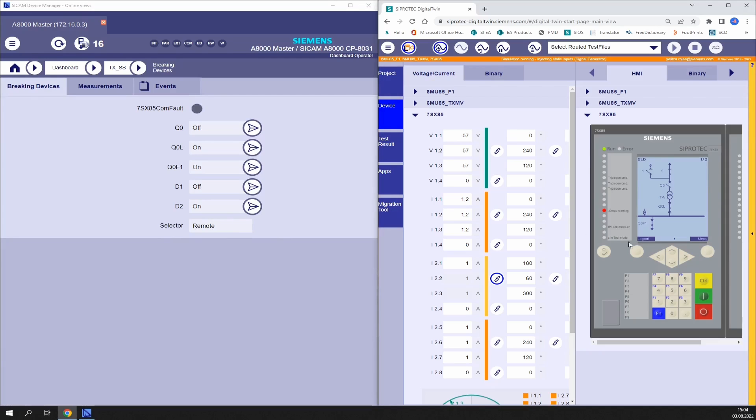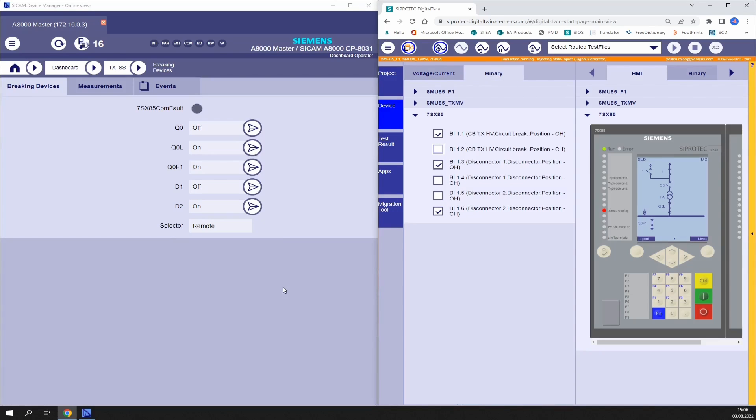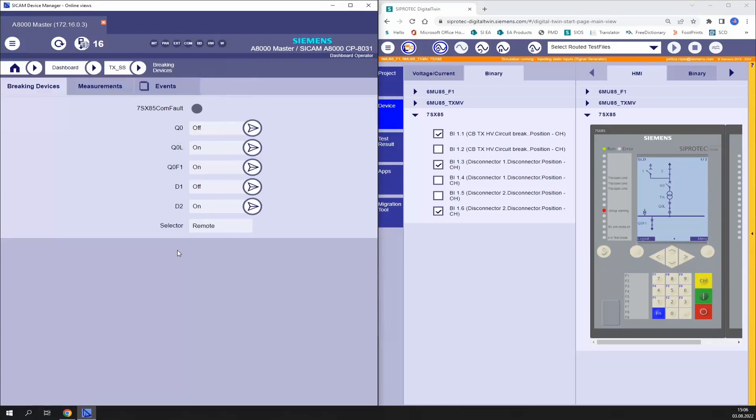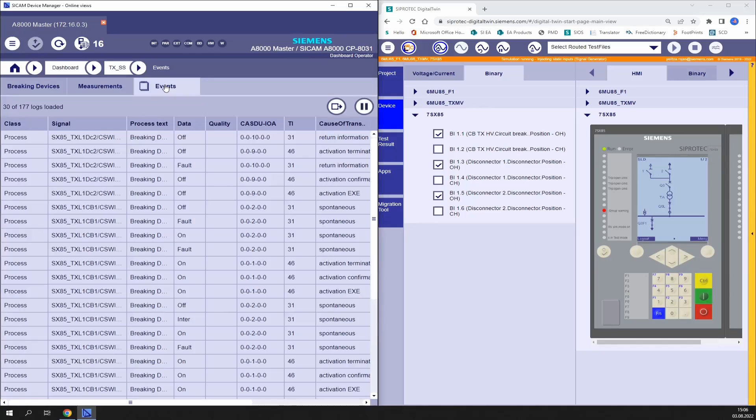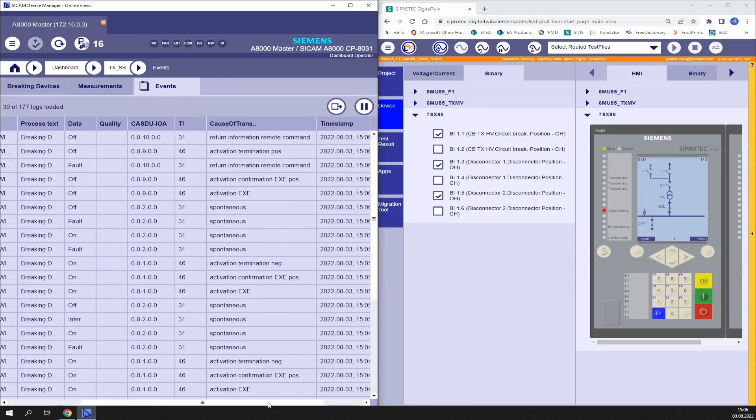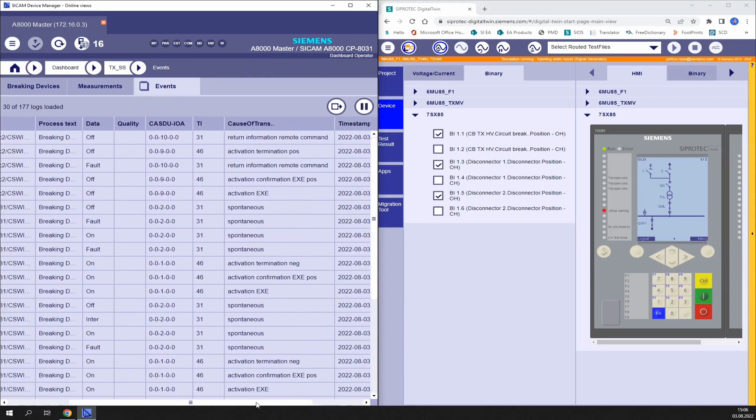Let's send a command for example to the disconnector. As the normal feedback for a disconnector takes some seconds, we can send an open request and really fast change the position by forcing the corresponding binary input to get the positive feedback in the RTU. Let's do it. So now it is open in the display and in the user interface of the SICAM A8000. And if we go to the event list we find the activation of the command in the open position and the positive feedback.